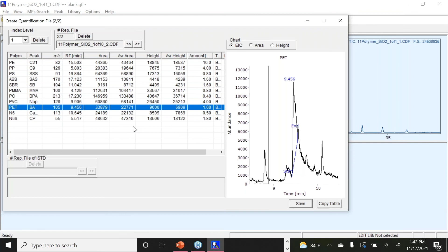So very quickly, you'll actually see the quantification file. This is where you can check and make sure everything looks good based on the standards that you ran. So you see the polymer name here. These are the characteristic peaks or the EICs, as I mentioned, the M/Zs that we extract for each polymer to be able to use the F-Search, retention time, area, and you can check each polymer and manually change that integration here. So you can click on PP and this is your first set. You can also go to your next sample and check and make sure everything looks good. Again, if you don't like an integration, you could easily change that manually for yourself.